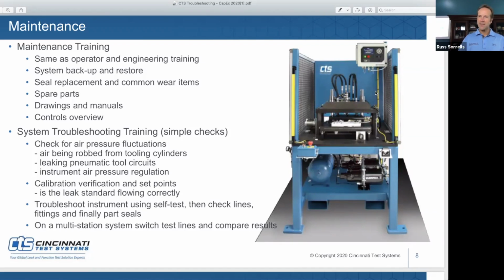And I said to the customer, unbolt this thing, let's look underneath this. Sure enough, they had gun drilled it. They tried to drill about 12 inches into this plate, and the drill had run out, and so it had exposed underneath. They had a hole in the bottom of their fixture essentially, and until the bubbles came bubbling out, it was one of those leaks you never can find. Sometimes it's tough. So yeah, sorry to get sidetracked on that. I just remember that because I was there for 6 hours as we tried to figure this out. Yeah, and like we just said, using your drawings to understand where the trouble spots could be.